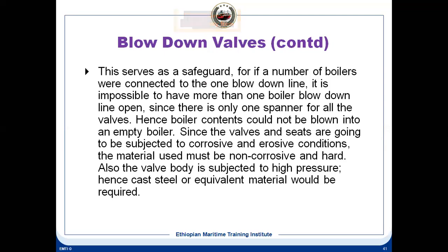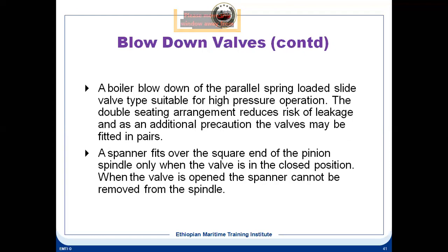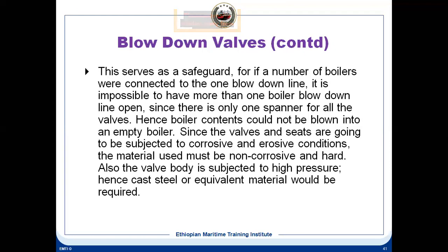So if you have more than one boiler, obviously the blowdown line going to the ship side will be common. The blowdown lines from the boilers will be joining at some point, and then the common line will be going down to the ship side. So you should not be able to blow down more than one boiler at a time. Hence this safety requirement of a spanner which can be fitted to only one blowdown valve at a time.